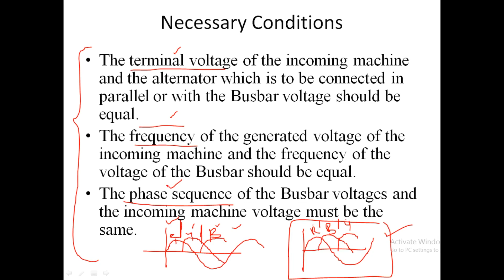This you may have studied in case of transformer also. There also we are discussing the same thing. Actually, in case of a transformer, it is not terminal voltage, it is induced EMF, because in a transformer the rated voltage is induced EMF E. So the condition will be like that only. E1 by E2, that turns ratio, should be same for both the transformers. And there will not be any condition like frequency. Instead of that, polarity should be same and the phase sequences should be same in case of transformers. But here the three parameters you have to note down. One is terminal voltage, another one is frequency, and the third one is phase sequence.